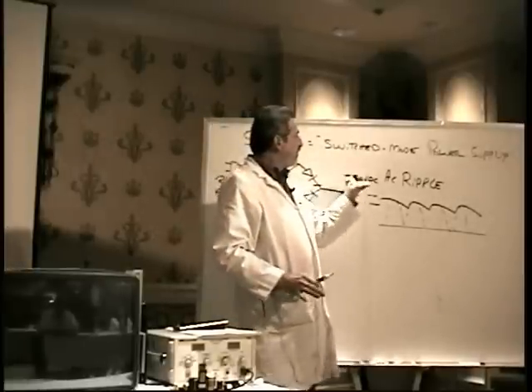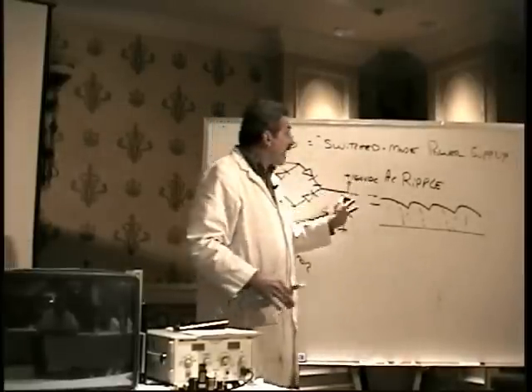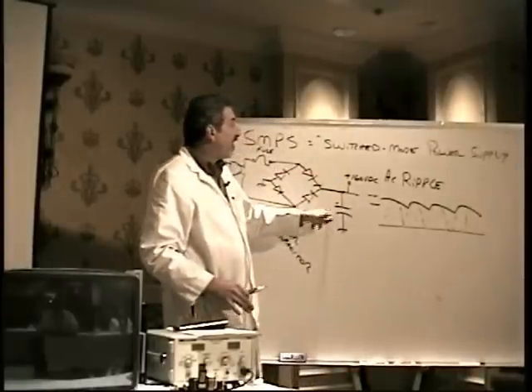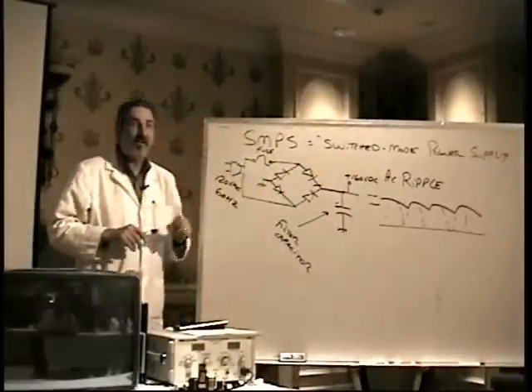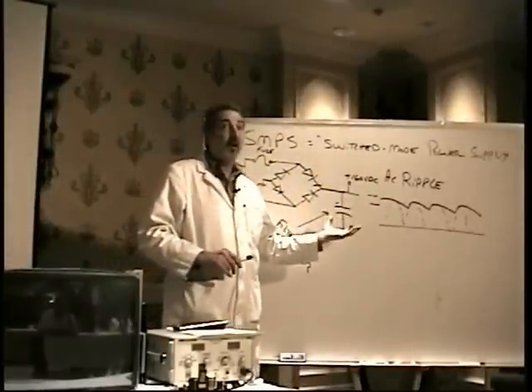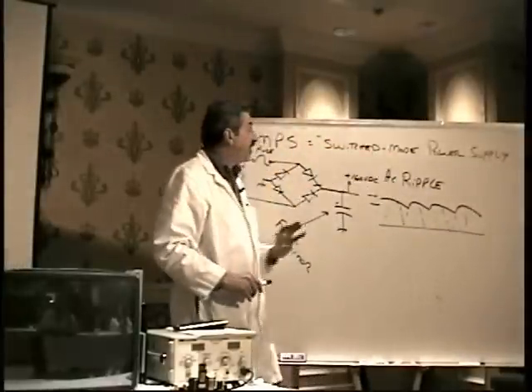Nothing could cause the voltage to read too high here, nothing failing, that is. But it is possible that the capacitor can fail and cause the voltage to read too low. One of the symptoms of a bad electrolytic capacitor, that's a filter capacitor in a power supply, is voltage that is too low, not too high.